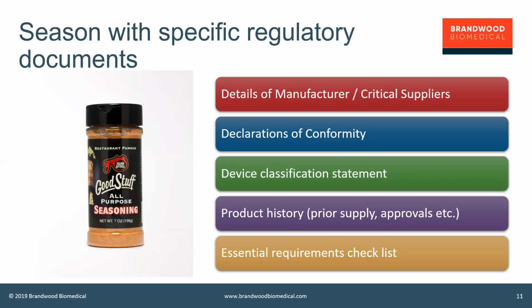And so having a regulatory strategy or a classification document that describes how you've made that classification determination, but also met the requirements and can show the specific clauses of the guidances that you have created that classification with is key.